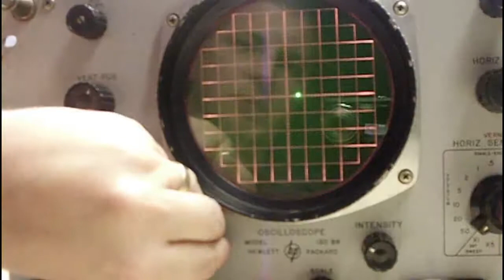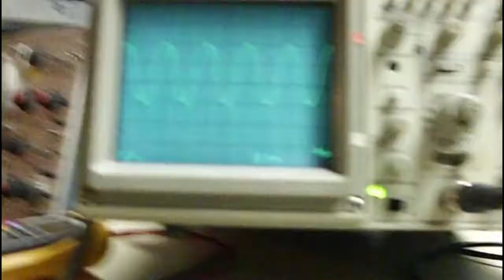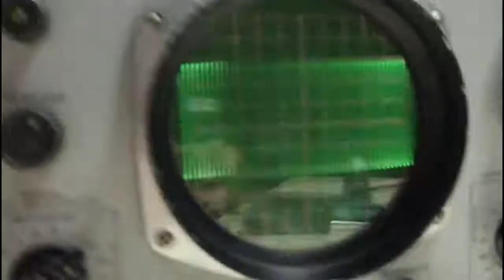Now let's see what that calibration looks like. Isn't that gorgeous? Look at that. It's beautiful. Absolutely gorgeous. Alright, so now we're going to adjust the calibrator. I've put in a 1 kilohertz signal. Here's the same signal that you're seeing on the other scope. It's exactly 1 kilohertz, and I've verified that with my frequency counter, and it's 300 millivolts peak to peak, as you can see here. Okay, and so here we need 6 centimeters of deflection, so I'm going to adjust R40, I think. Yep, adjust R40 to get 6 units of deflection. So here's R40. So I'm going to make this adjustment.